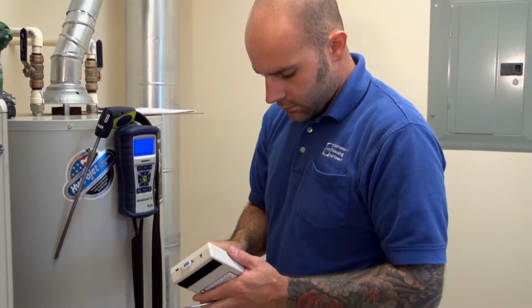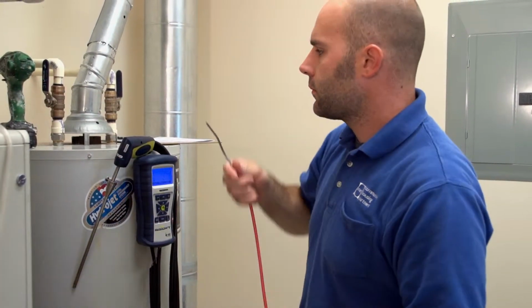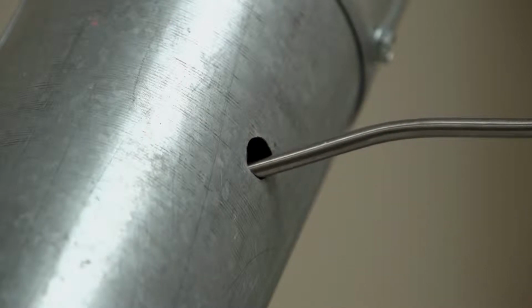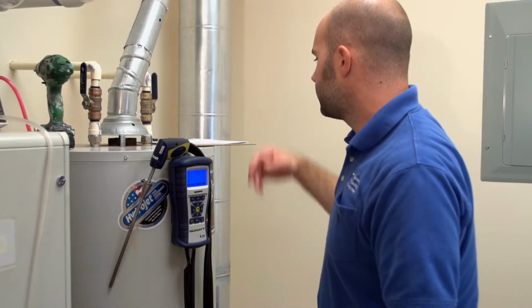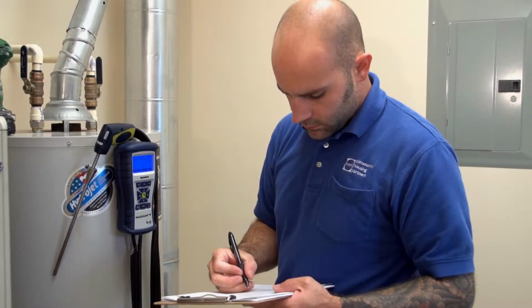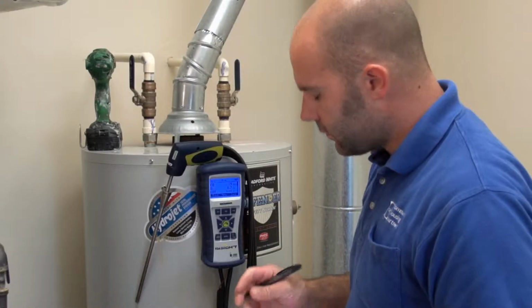Insert probe into the flue stream 1 to 2 feet above the draft diverter and read pressure from channel B on the manometer. This reading should be compared to the minimum acceptable draft test range calculated earlier and is based on the ambient temperature outside. This measurement can be taken directly after spillage but will only improve as the appliance nears steady state. BPI standards state that draft can be taken at the appliance's steady state efficiency or the 10-minute mark.